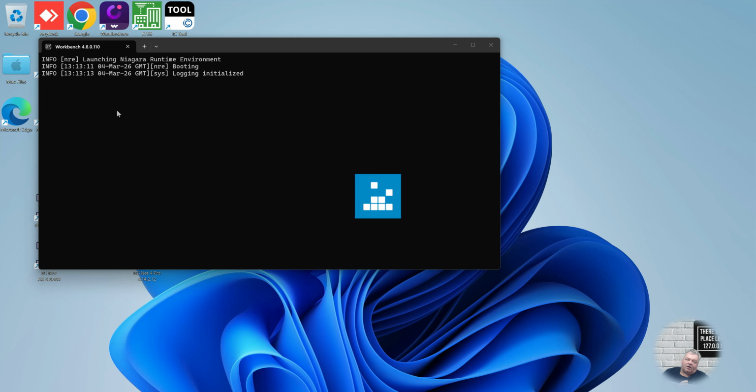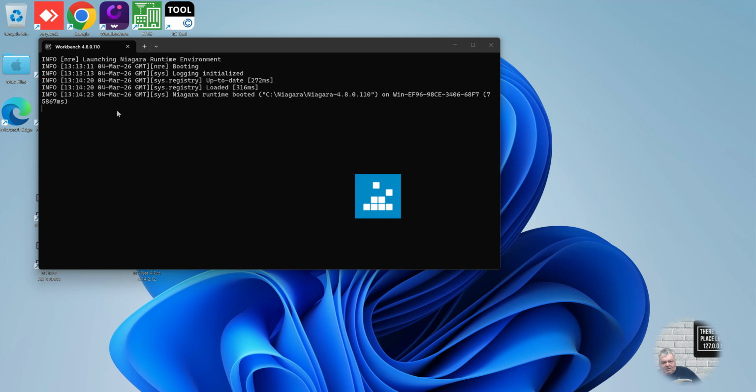Write the logic in the lowest version so that it can easily on site be sent to the engineer, and whatever version he's got, he's not going to have anything lower than 4.8, or he shouldn't have. He probably has 4.15 currently, but he may have 4.14 or 4.11. So it's just easier for them to take that file and load it in depending on what he's commissioned the station at. So we're loading this one up at the moment.